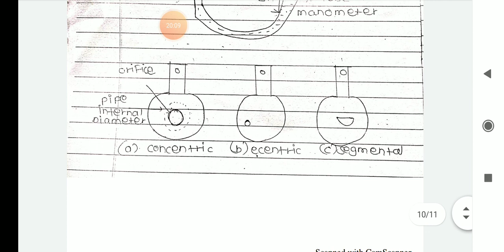Second one is the eccentric orifice plate. In the eccentric type, the hole is located at the bottom of the pipe. It is used for measurement of flow of solids, water, oils, etc. Third one is the segmental. It is similar to the eccentric, and in this orifice plate only a half circular hole is present, as you can observe in the diagram. It is used for the measurement of liquids, air or particular materials.